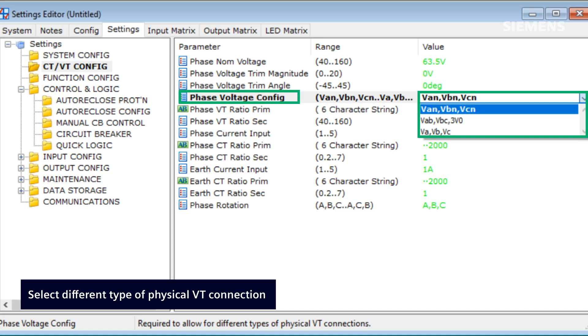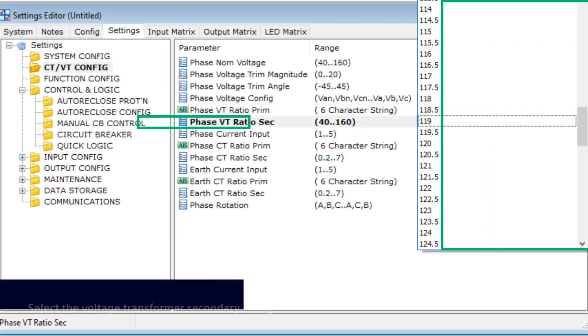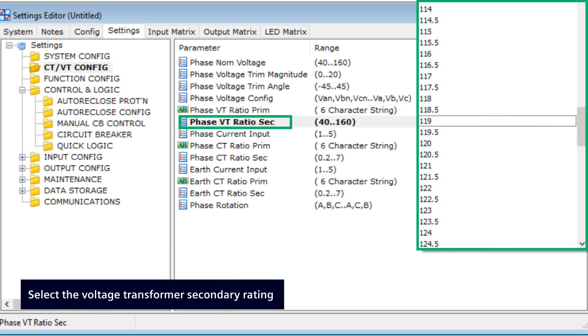The phase voltage config setting permits the user to choose the appropriate physical VT (voltage transformer) connection type based on the system requirements. The phase VT ratio primary setting enables the user to select the primary rating of the voltage transformer, which is used to scale the primary voltage measurement within the instrument based on the transformer ratio. The phase VT ratio secondary setting permits the user to specify the secondary rating of the voltage transformer, which is utilized to determine the appropriate ratio for scaling the primary voltage measurement within the instrument.